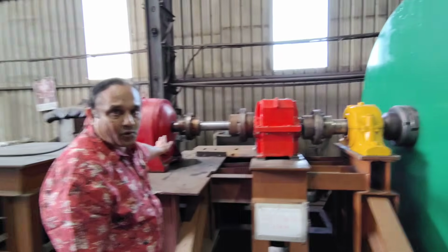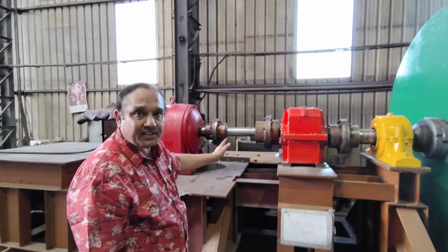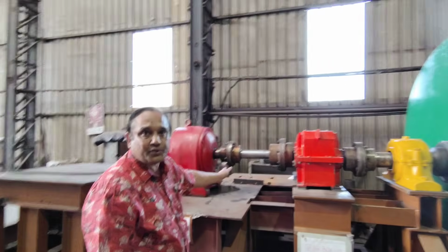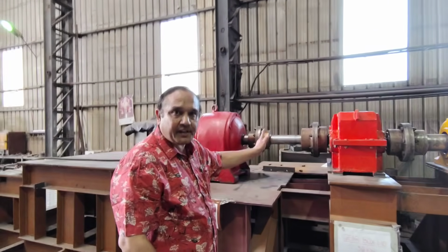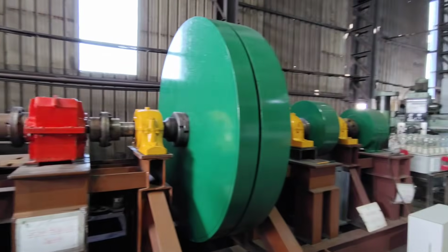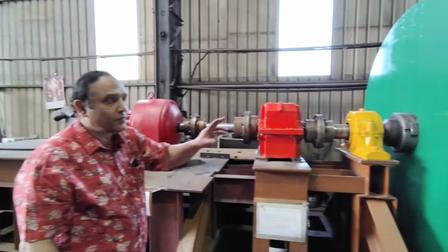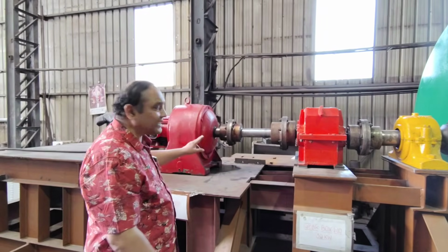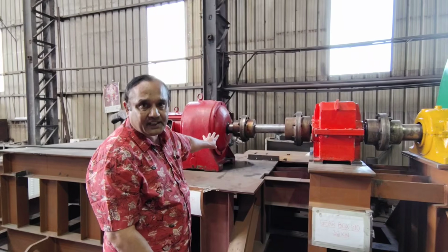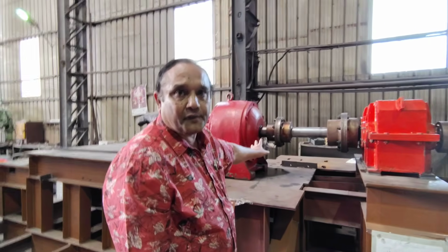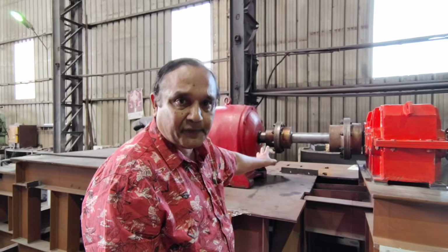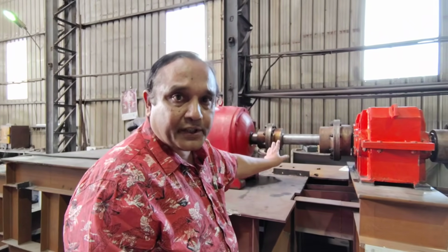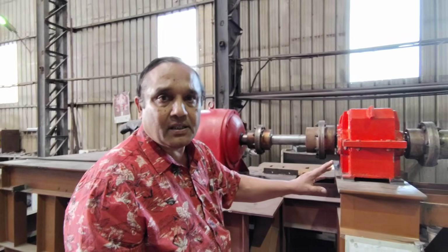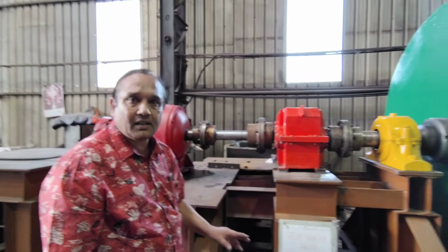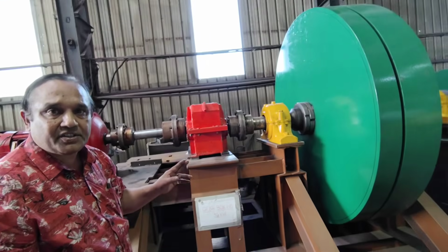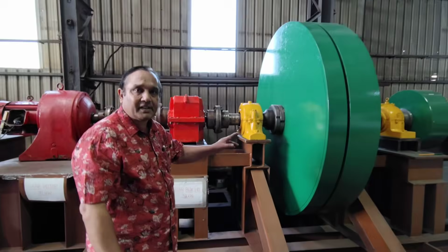So the motor is 30 kilowatt, and in the actual engineering specifications, here also one should have 14 ton. So the 14 ton over here and 14 ton over there will synchronize the system. But as of now, only one side has 14 ton and the other side is empty. The 30 kilowatt, 50 hertz, 415 volt 3-phase motor is going to rotate a 14 ton mass, 2 meter diameter disc flywheel at 280 rotations in the coming time.